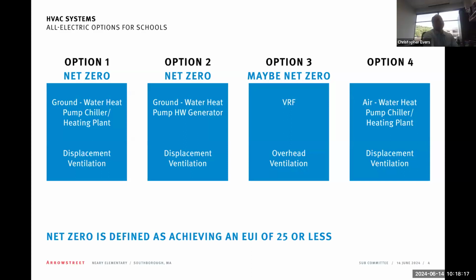Yeah. So that part of it is still quite efficient. The electric boiler is the very inefficient side of that, and that's why the EUI tends to be higher. What about a cooling tower with a water cooled centrifugal? How does that weigh in? Again, that would be on the chiller side, so that would probably be similar, maybe a little bit less efficient. But again, for a school, it still is predominantly heating load dominated, and so the electric boiler is getting quite a bit of use.